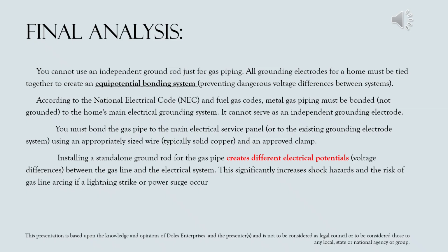I've seen this happen also where I had a guy once many years ago. They wanted to have a bond for the pump motor on a Whirlpool tub under a house, and the inspector wanted him to run another ground rod and run a conductor from the bonded clamp or the grounding clamp on that motor to that ground rod, independent of everything else. And again, this flies in the face of the whole purpose that we do equal potential bonding for the house. All grounding electrodes for a home must be tied together to create equal potential bonding. Again, we want uniform voltage, either increase or decrease.